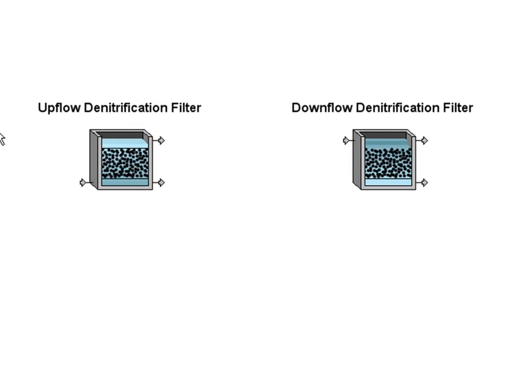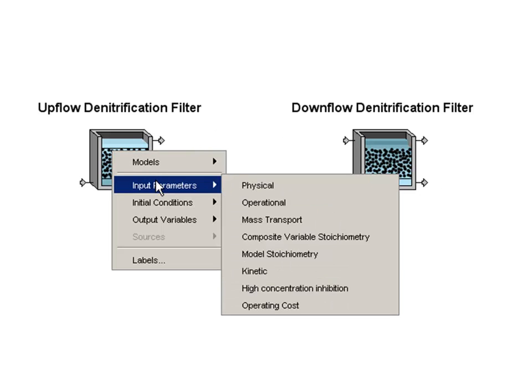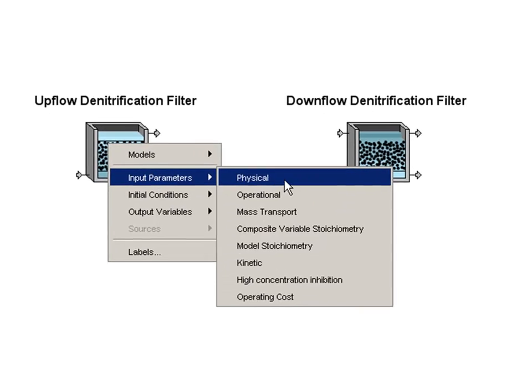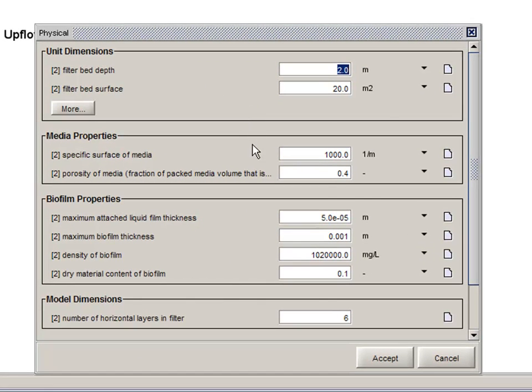We have added upflow and downflow denitrification filters for tertiary nitrate removal. These follow the same type of biofilm model that we've used in our other objects, where you can specify the specific surface area and porosity and fill of the media.